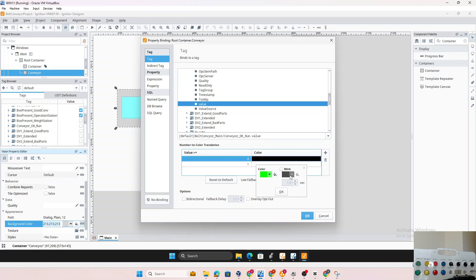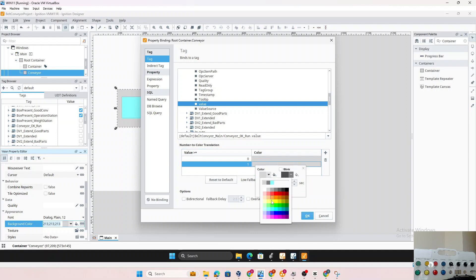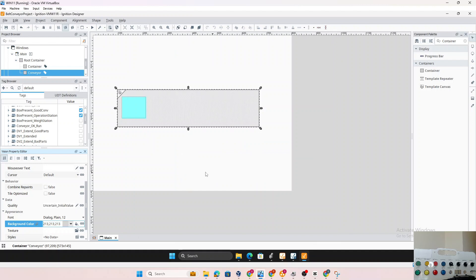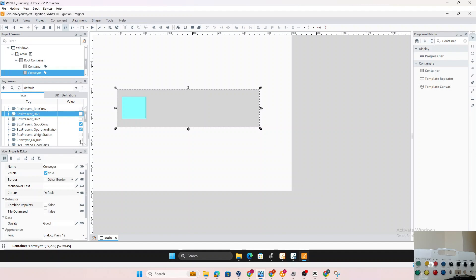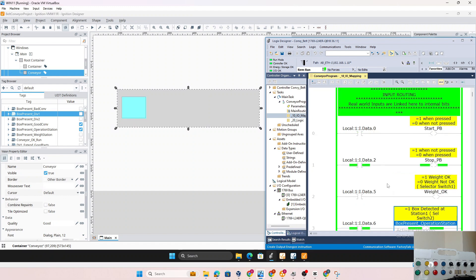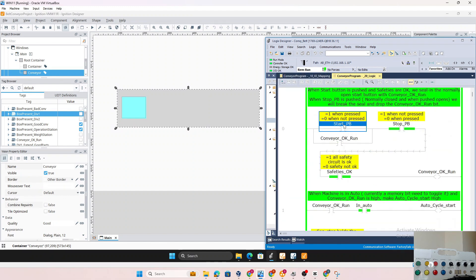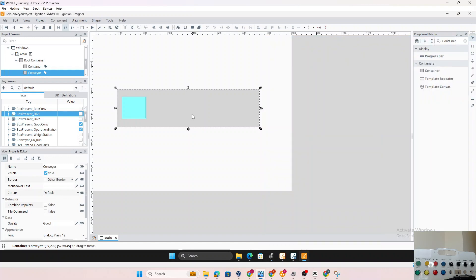We set up the color expression: when the value is 1, make it green; when the value is 0, keep it gray. Click OK. Since the conveyor is currently not running — you can see 'Conveyor OK Run' has no checkmark — we wait for the start condition from the PLC. Once the start button is pressed, the conveyor OK run bit comes on and the display changes to green. That's how we show the conveyor is running.